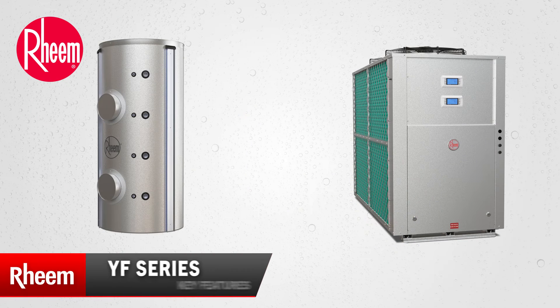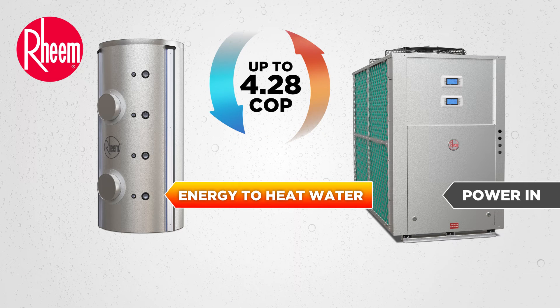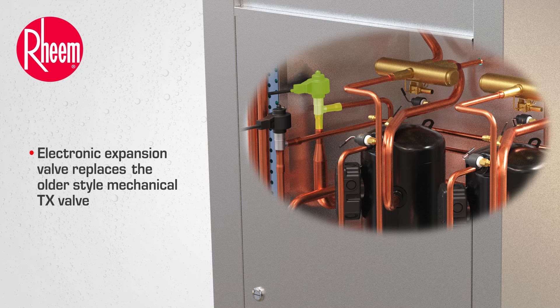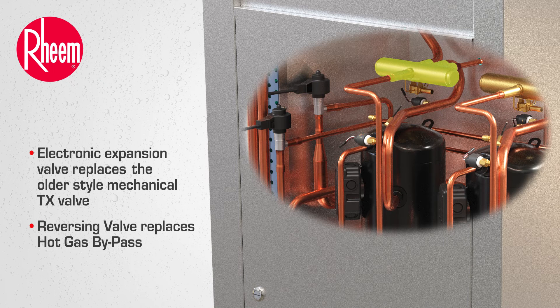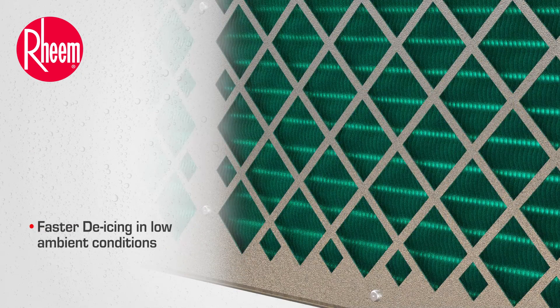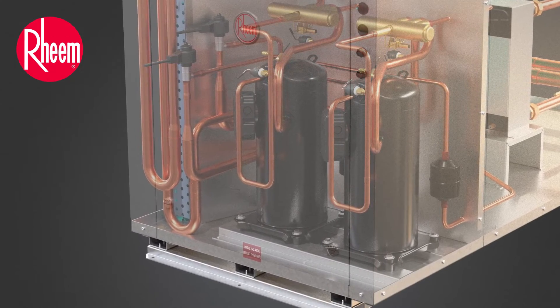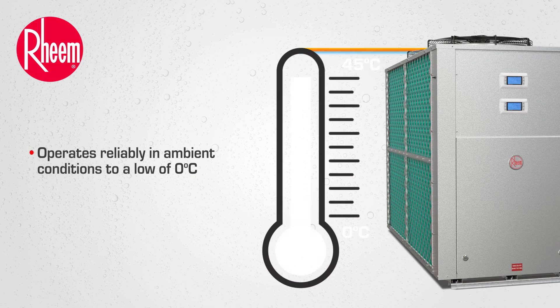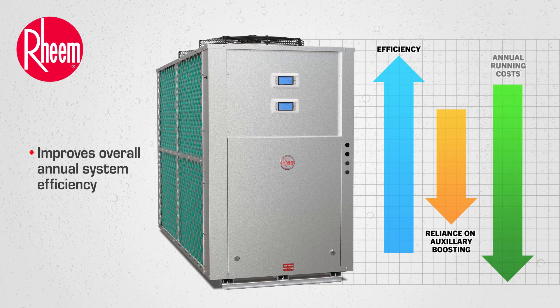The Rheem YF Series has been developed for higher coefficient of performance by tuning the performance in our on-site psychrometric chamber. An electronic expansion valve replaces the older-style mechanical TX valve. And a reversing valve replaces hot gas bypass, providing faster de-icing in low ambient temperatures. Further product enhancements allow the YF Series heat pump to operate reliably in ambient conditions to a low of zero degrees C, reducing the reliance on auxiliary electric heating element boosting, which improves overall annual system efficiency.